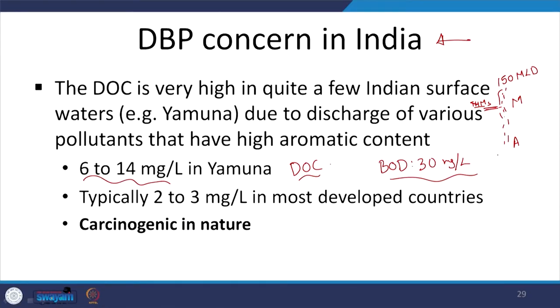In Agra, they were using an MBBR (moving bed biofilm reactor) which did a very good job removing BOD and COD. But even there, DOC was pretty high and DBP concentrations were remarkably high — comparable to Mathura's traditional treatment plant. The chlorine doses at Mathura required pre-chlorination at almost 100 mg/L to prevent microbial growth in sedimentation tanks — illustrating the extreme doses being used.